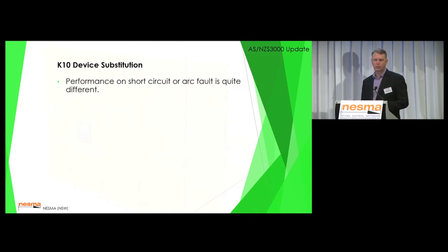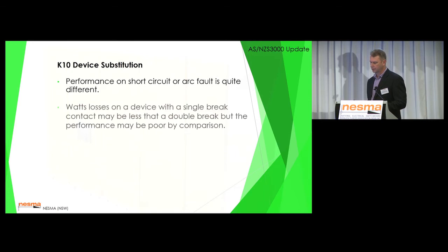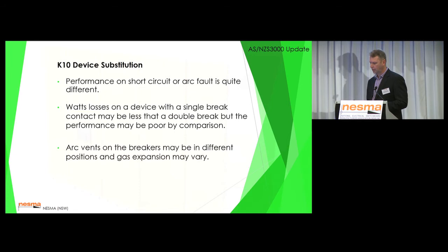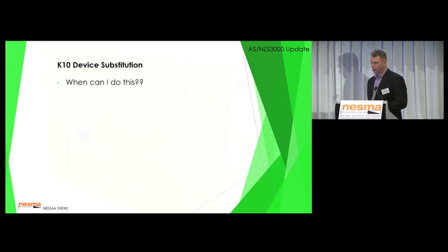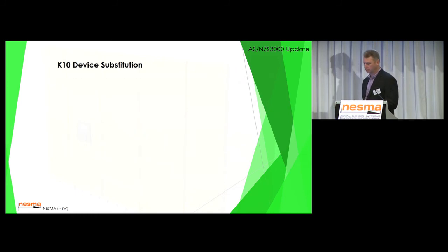Performance on a short circuit or arc fault can be quite different. As I said, watts losses on a single break device might be lower than those on a double break, but its performance under short circuit may be poorer. Arc vents on breakers may be in different positions, and gas expansion may vary. So when can I do this?